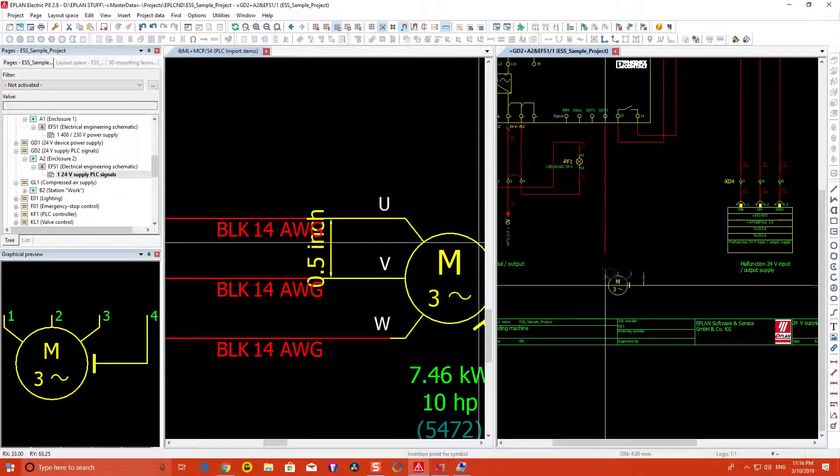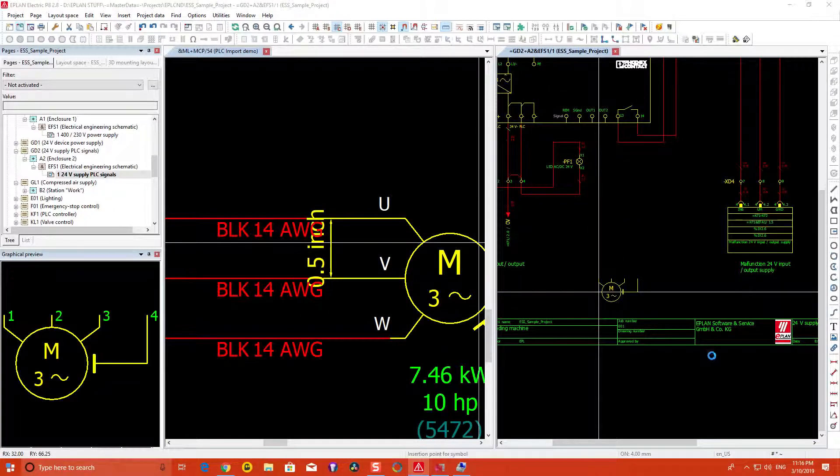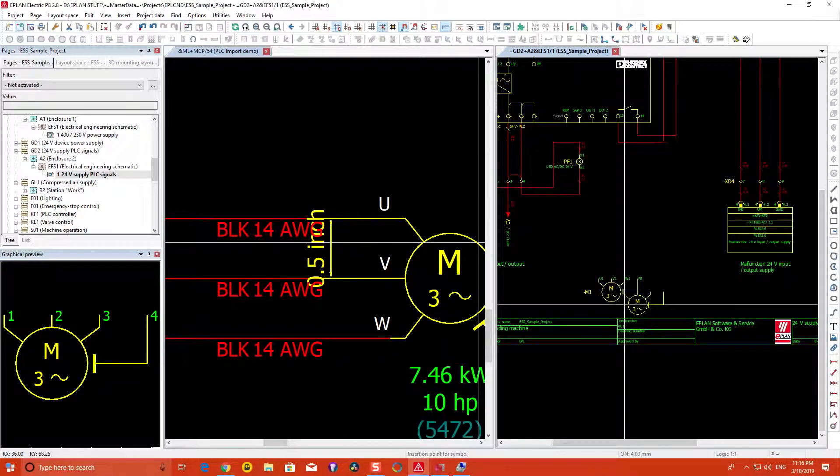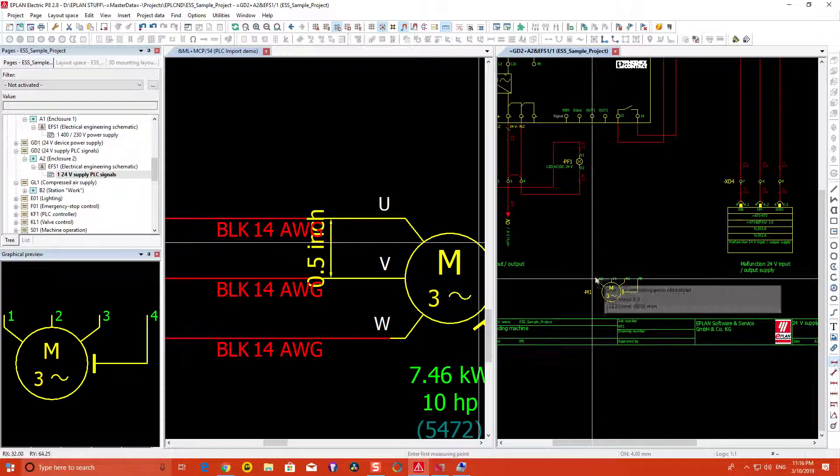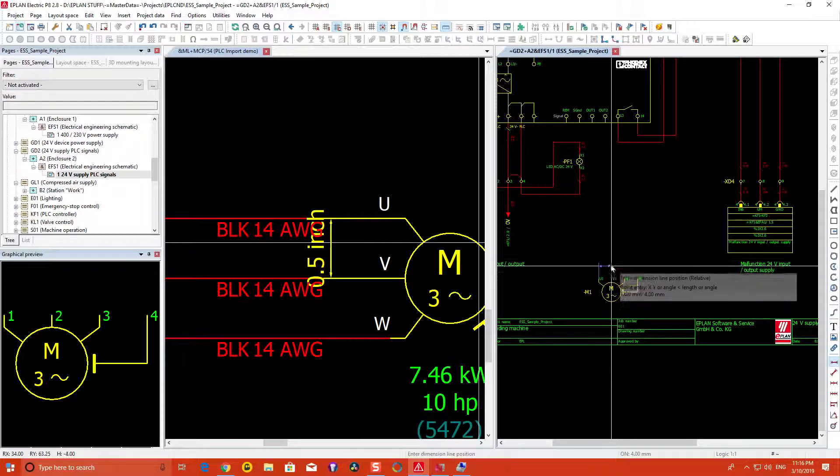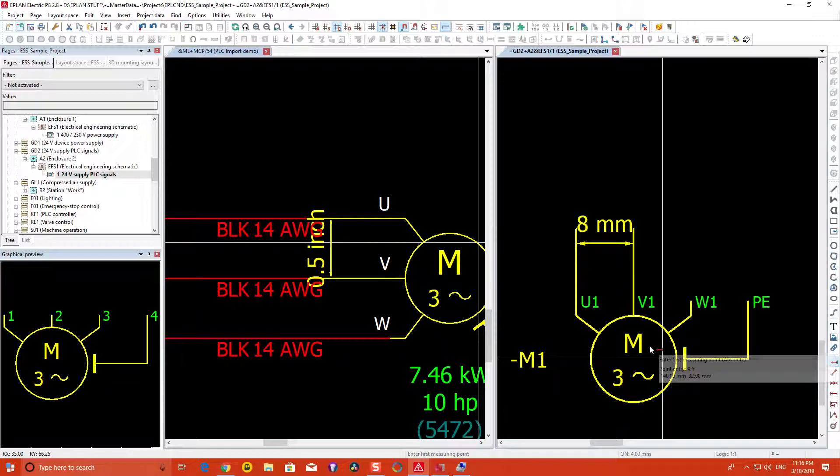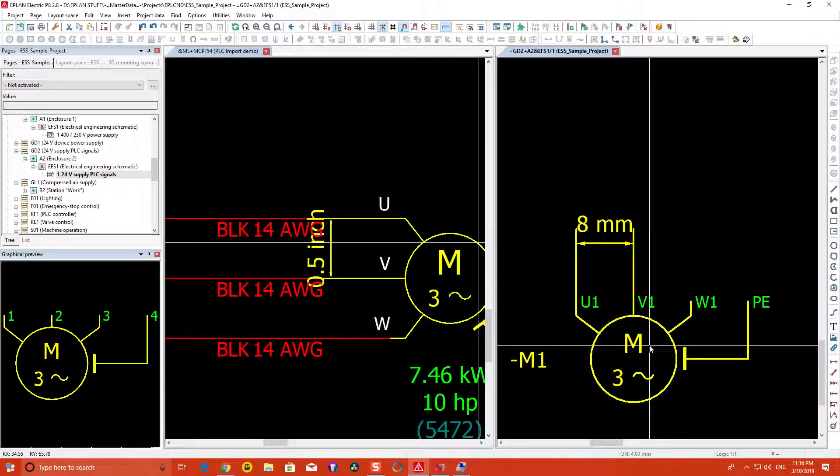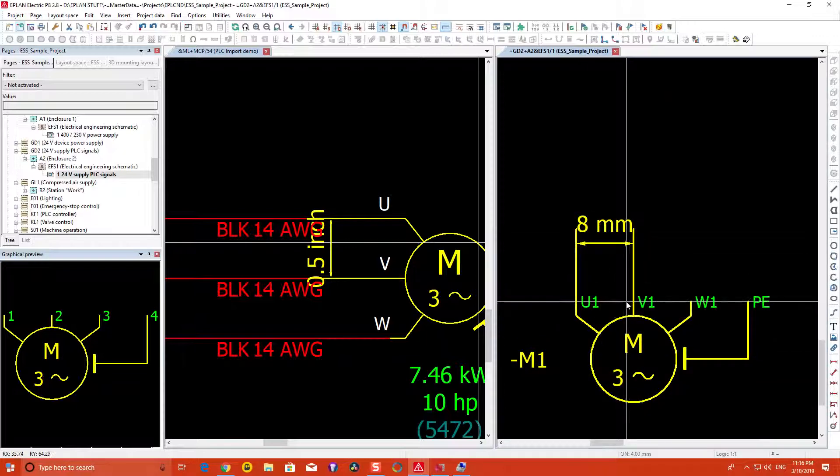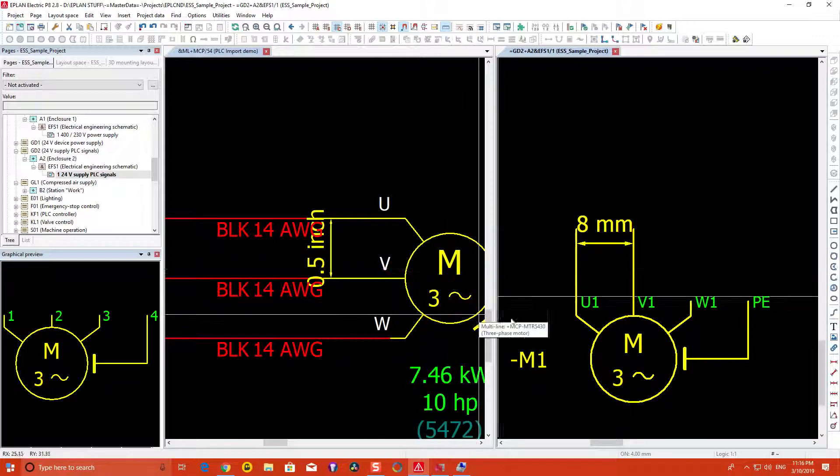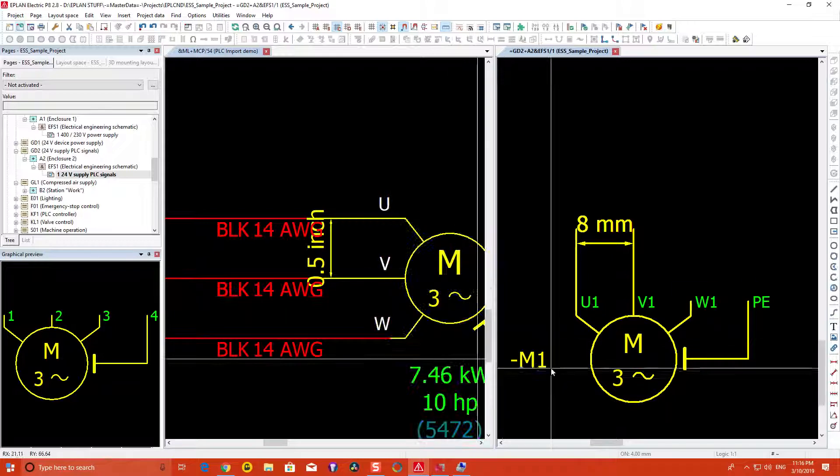I'll grab an IEC motor here and place it down. If I do the same dimensioning check, you'll notice that between two connection points there is eight millimeters apart. This really plays when we're doing our schematic and also when we're doing auto generation using the PLC tools.